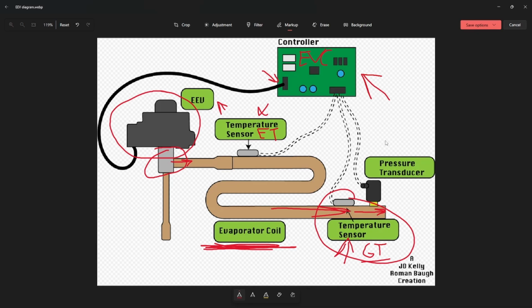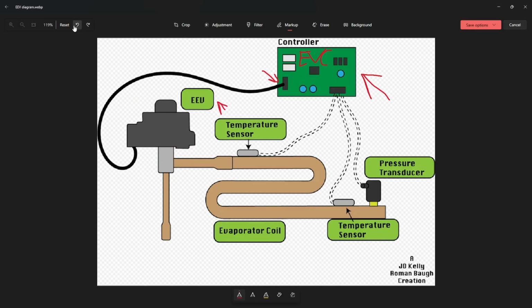And not every manufacturer uses this guy. Pressure transducers are not on every single piece of equipment that uses an EEV. Pressure transducers give our control board the pressure value of the evaporator or suction side. Why you would use a pressure transducer is for different operation modes of our system.